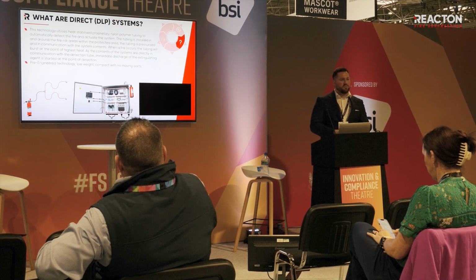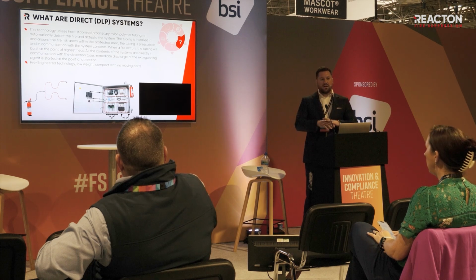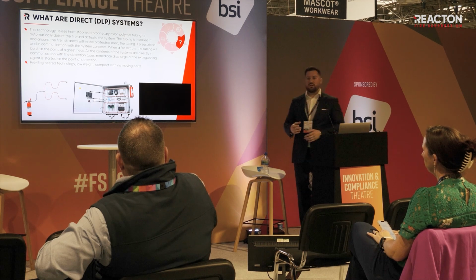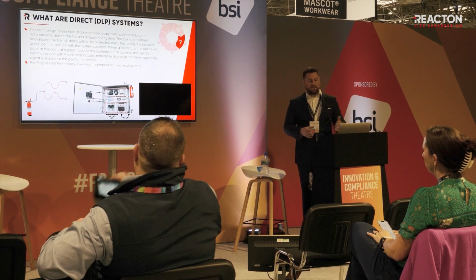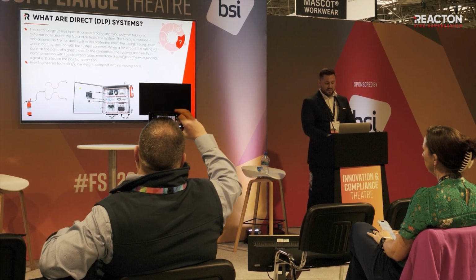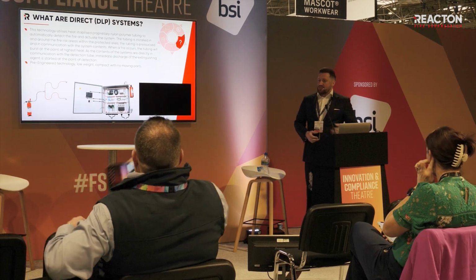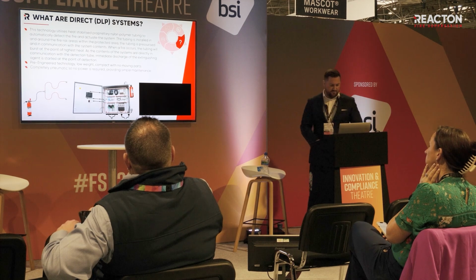They're all pre-engineered. When I say pre-engineered, this is a term that we use in this industry for products that have all the testing done up front, and as long as you design it in accordance with your technical manual, you can install it without having to do any complex design work, hydraulic calculations and verifications. It's low weight, there's no moving parts, extremely compact, so these can fit right next to the hazard that you have.